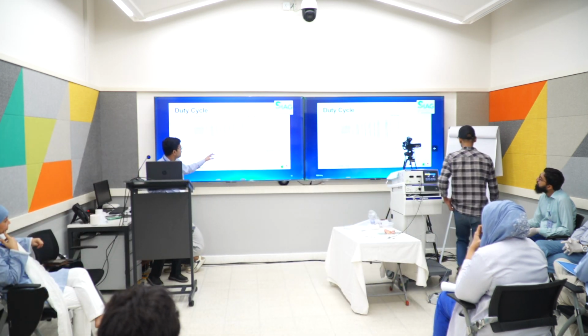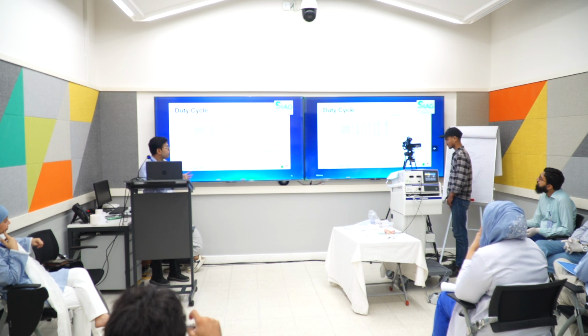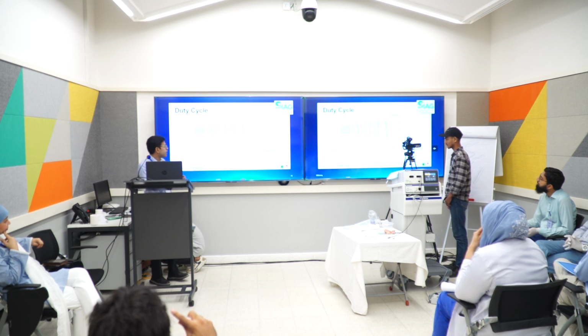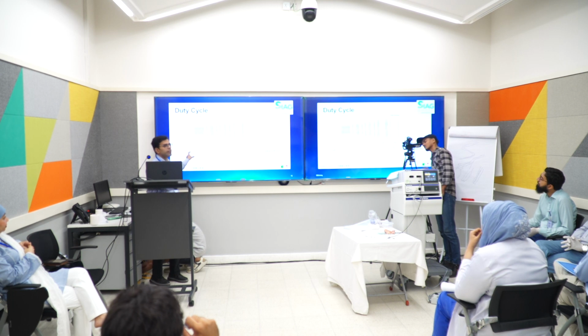In between we have blend 1, blend 2, blend 3. You always see them on the machine, but we are unable to appreciate what they actually mean. So if we talk about blend 1, there is flow of current during 50% of the cycle. In blend 2, it's 40% of the cycle, and in blend 3, it's just 25%. So the longer the current flows, the more the cutting technique.